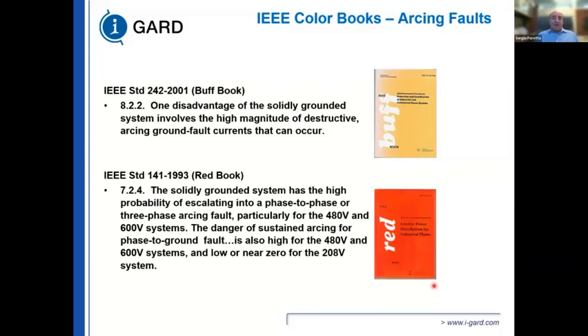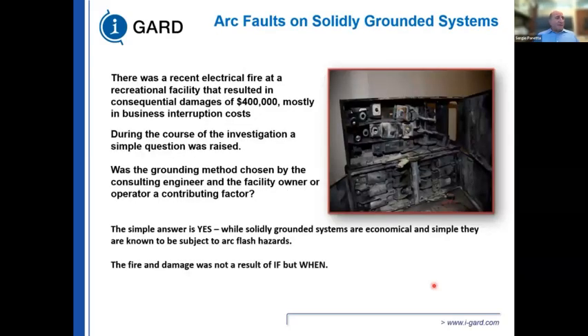Solid ground systems have a high probability of escalating to phase faults. Now you have 40, 50,000 amps of arcing current flowing through a ground fault. You're going to deteriorate the insulation. You have molten copper or aluminum, molten steel, debris. That's going to deteriorate the insulation between the phases. And when you deteriorate the insulation between the phases, you've now converted that ground fault into a phase-to-phase fault, and it could develop into a three-phase fault. This is why ground faults on solidly grounded systems can propagate to a three-phase fault very quickly if you don't trip right away.